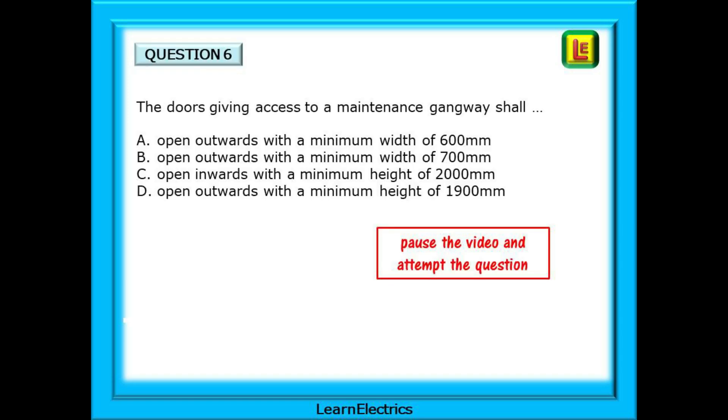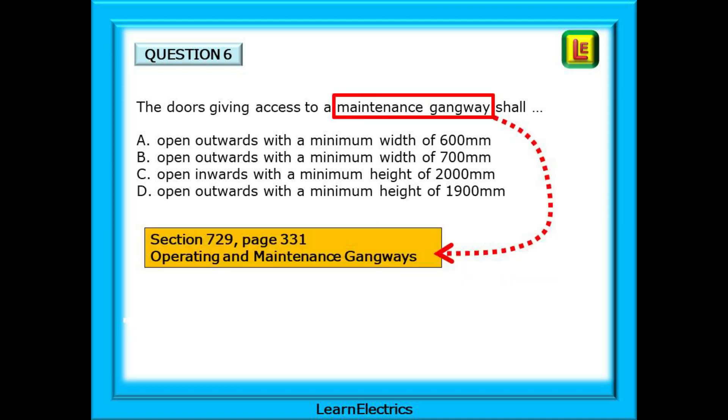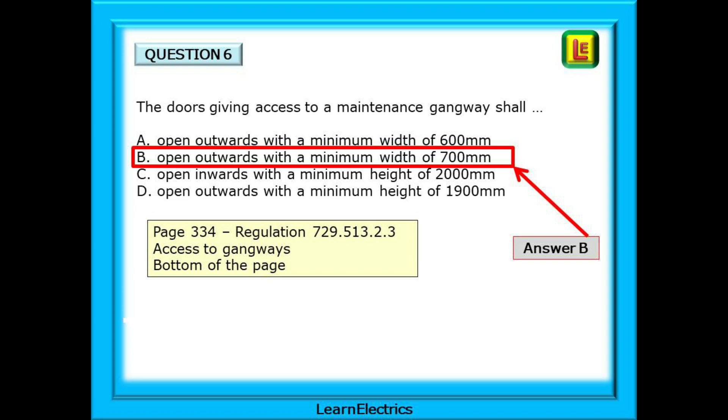Moving on to Question 6: The doors giving access to a maintenance gangway shall... and then 4 statements to complete the sentence. Pause the video and attempt this yourself. The clue is in the question: Maintenance gangway. And on page 3 we will find section 729, Operating and Maintenance Gangways. It is telling us to go to page 331 so let's do that. Within the pages of section 729 we come across page 334 and Regulation 729.513.2.3 which talks about access to gangways as mentioned in the question. At the bottom of page 334 we will find our answer. The only one that matches the book is answer B. Doors giving access to maintenance gangways shall open outwards with a minimum width of 700 millimetres. Answer B.